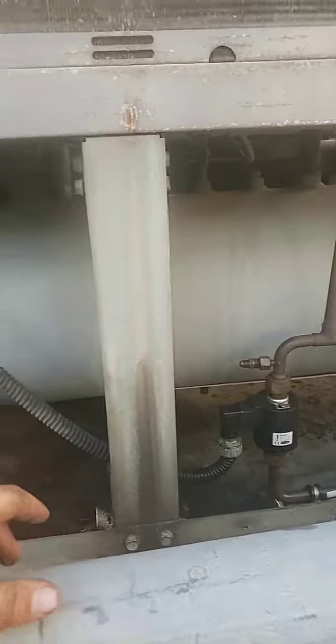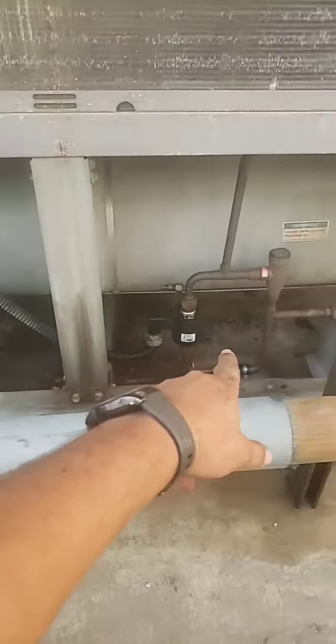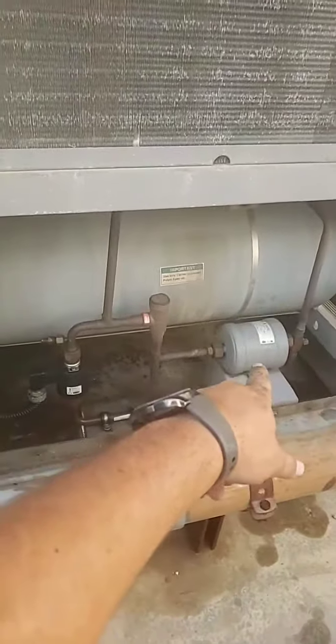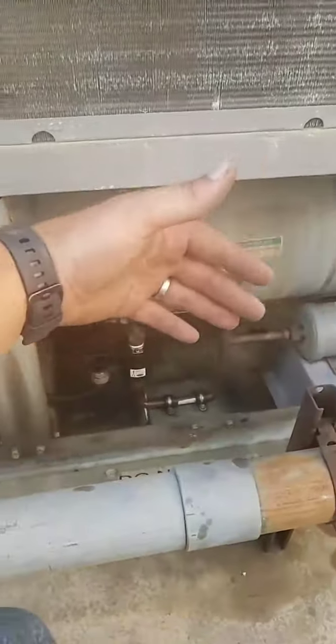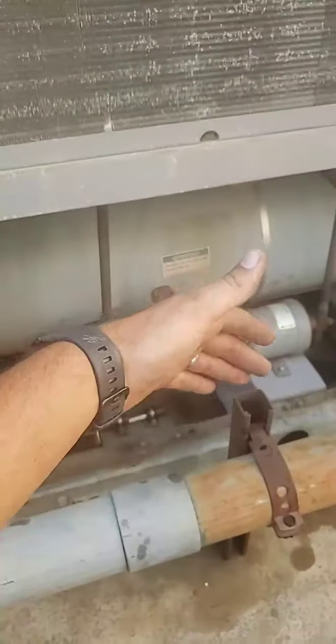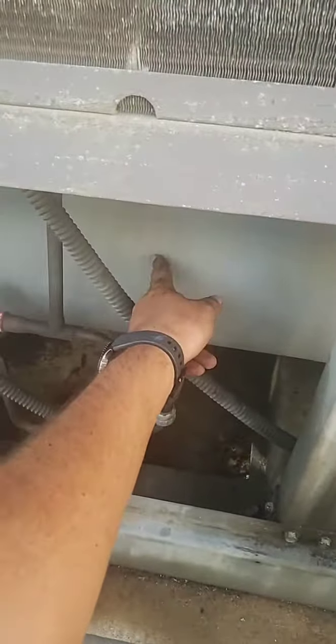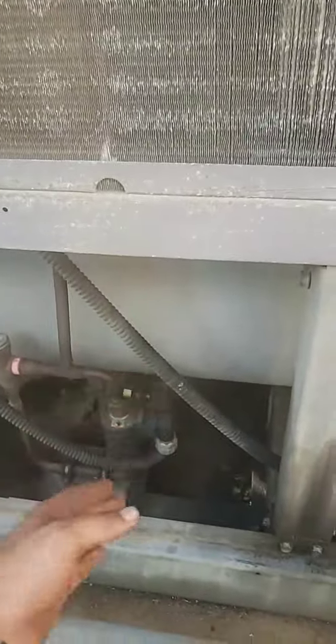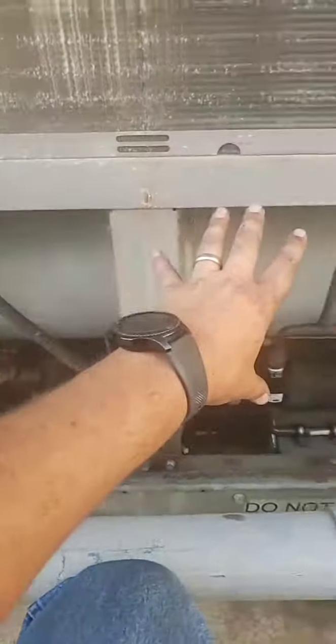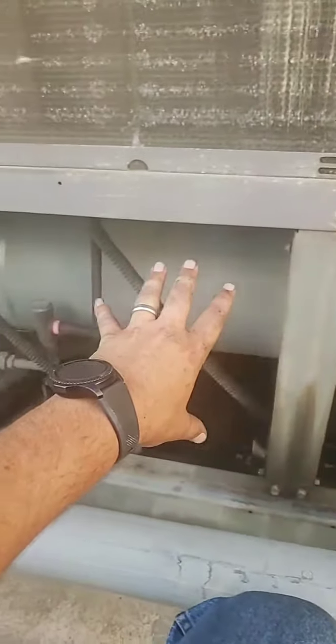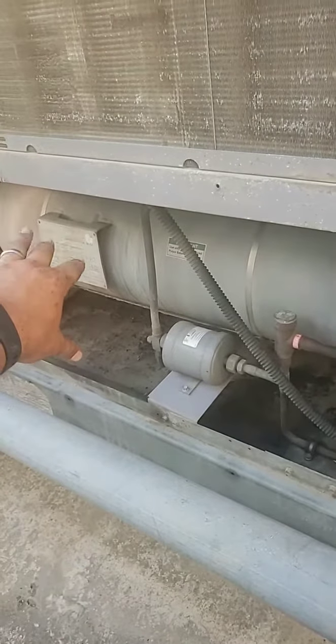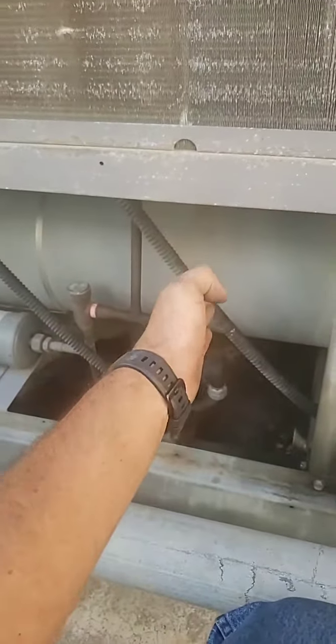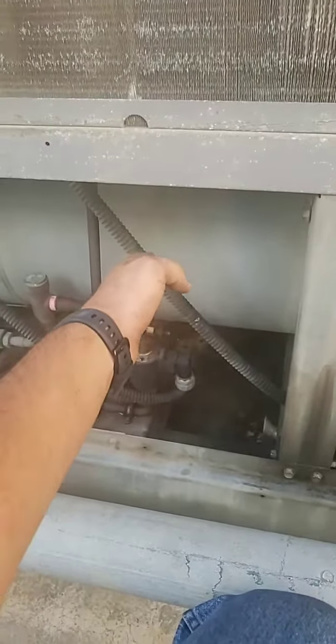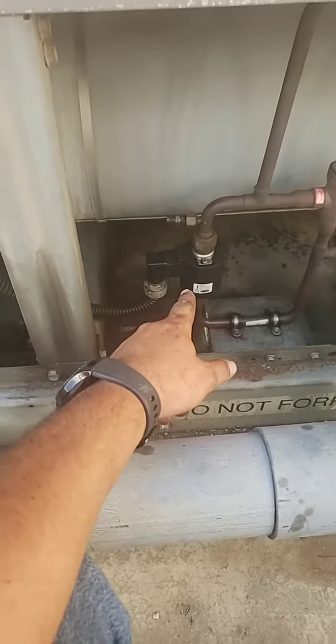So this here is your oil separator. These are your oil pumps, oil filters. So this is an external filter. Like I said, you've got an internal and an external oil filter. All right. Now right here where you see these welds are, that is where the refrigerant circuits are divided. So the whole system has an oil separator that does the whole unit together. But again, the circuits never mix. They are completely separated by that divider.